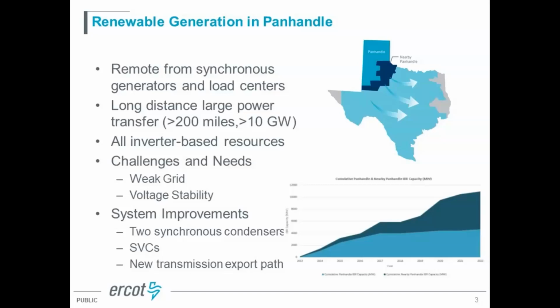Over the last few years, these are the typical options that have been conducted and identified, even implemented, in West Texas to improve the operation of renewables under weaker grid conditions. First, through PSCAD studies conducted a few years ago, we identified that under a weaker grid the controllers could not operate functionally; they needed a more robust signal. As a result, we implemented two synchronous condensers, particularly located in the panhandle region, to provide system strength and dynamic reactive support to improve voltage stability and system strength at the same time.